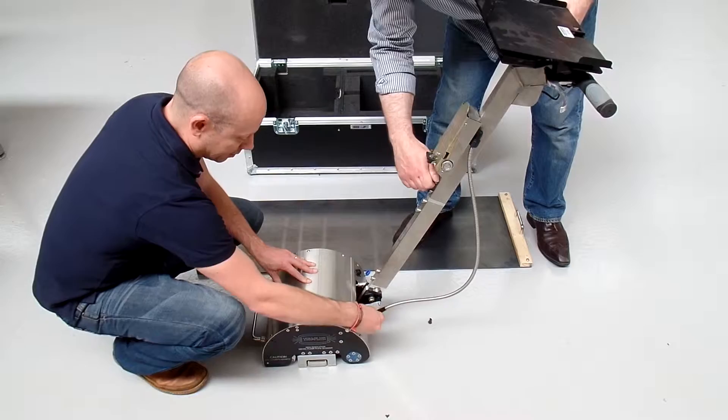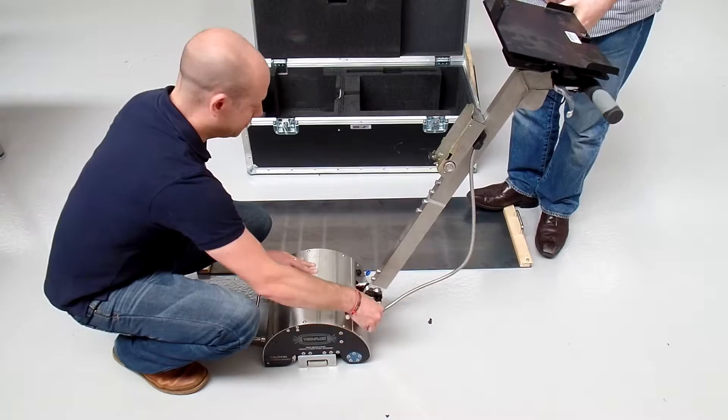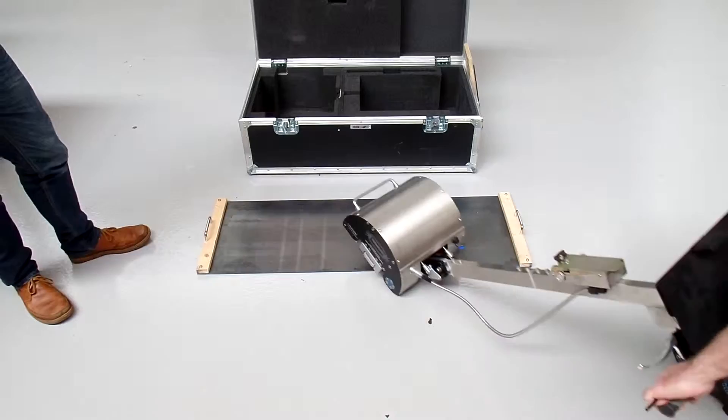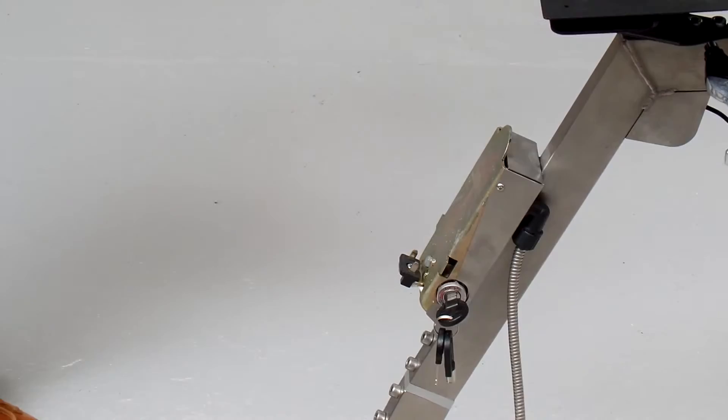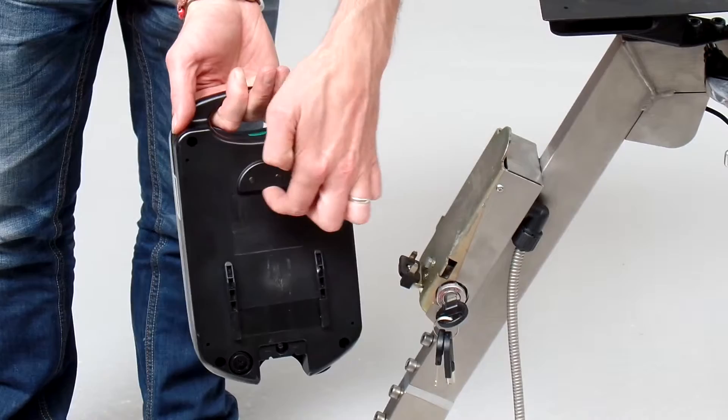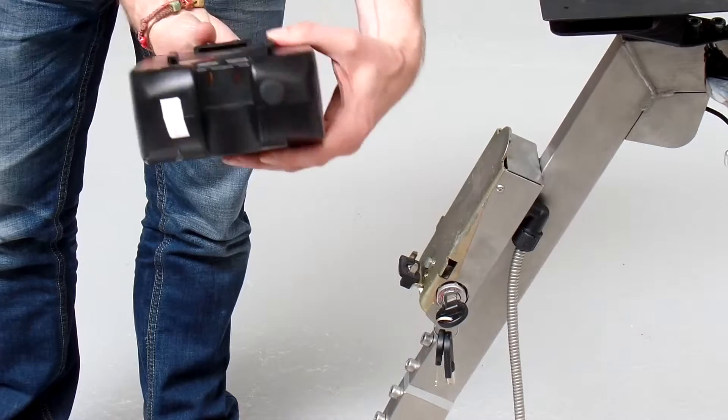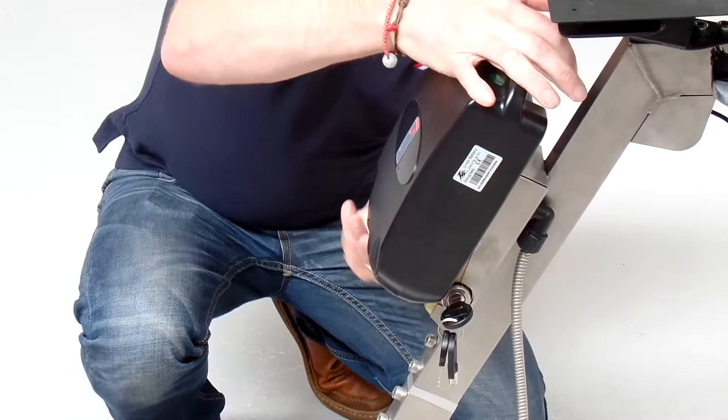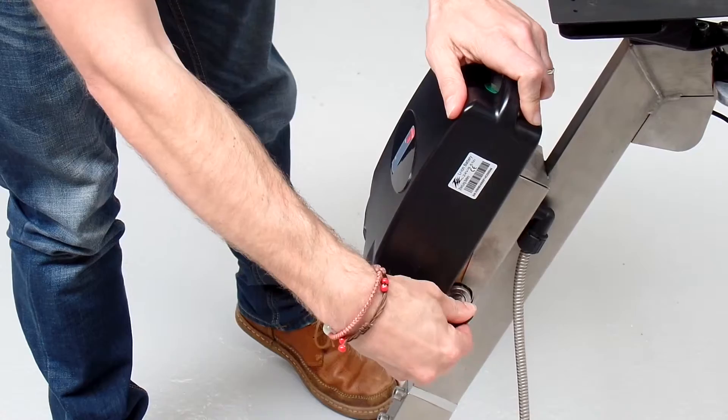This supplies power for the motors and is clipped into place. The TruFlex can then be wheeled onto the calibration plate to start the calibration. Take the battery from its flight case and connect it to the TruFlex unit. There is a plastic tab here which has to locate on the metal tab here, and the contacts are on the base of the battery like so.